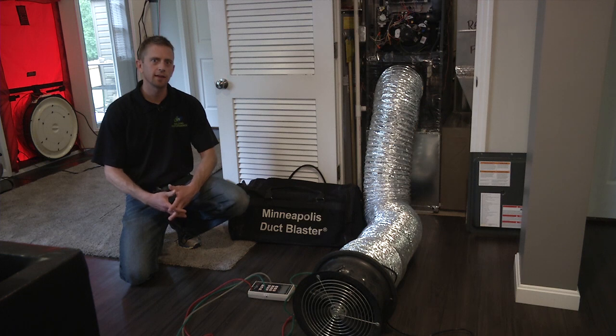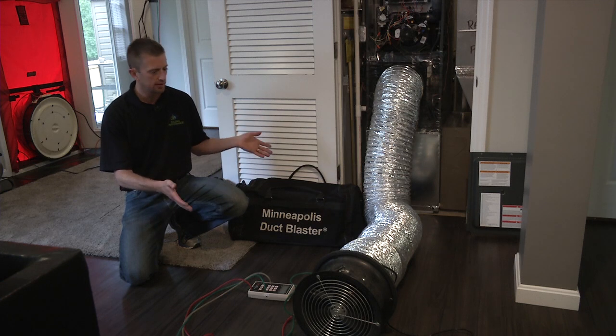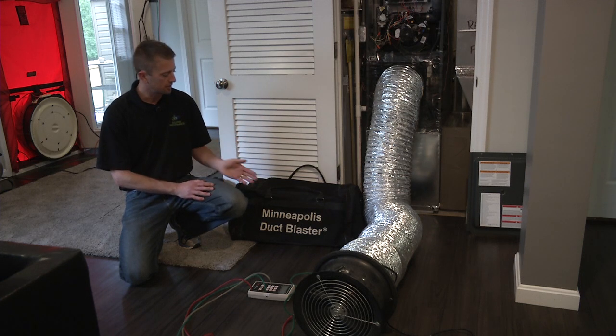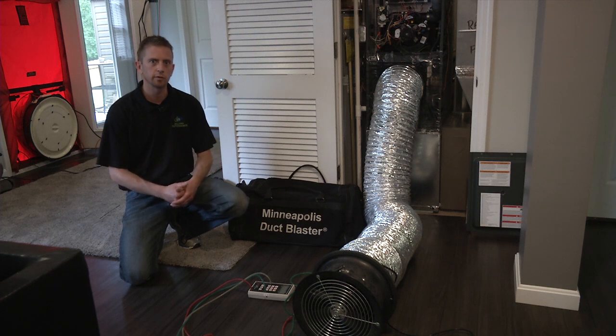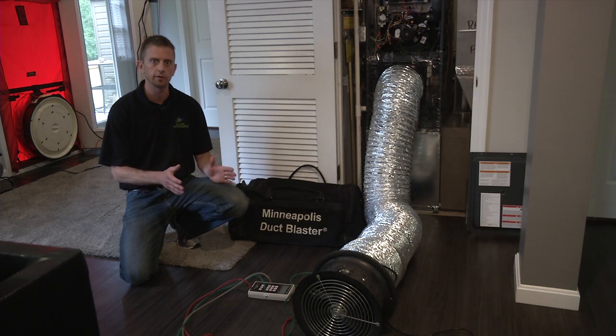Alright, so now we're inside the house and I'm going to show you the equipment that you need to have to do a duct leakage test. The first piece of equipment is the Duct Blaster. We use the Minneapolis Duct Blaster. There's also a Retrotec model. Basically what this does is it allows me to do a couple different tests. For code compliance, you can do a duct leakage to outside test, or you can do a total leakage test.